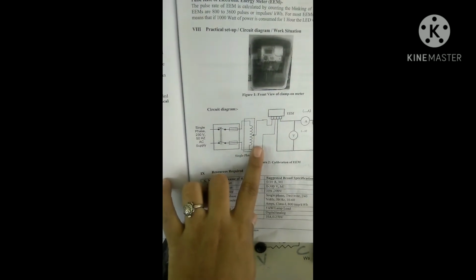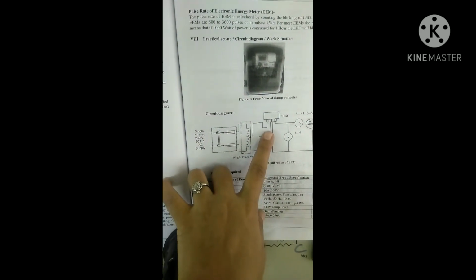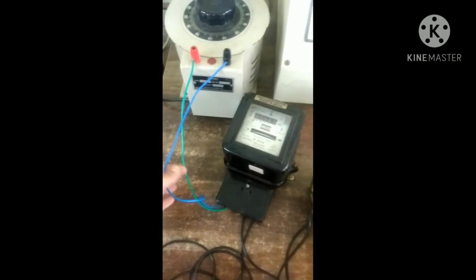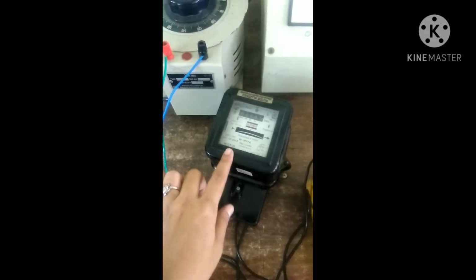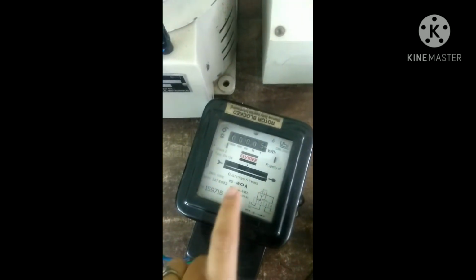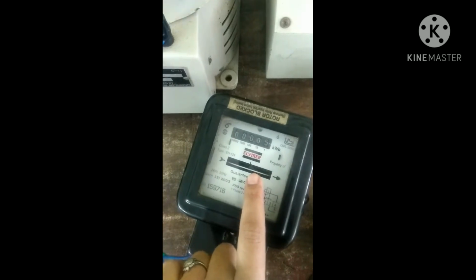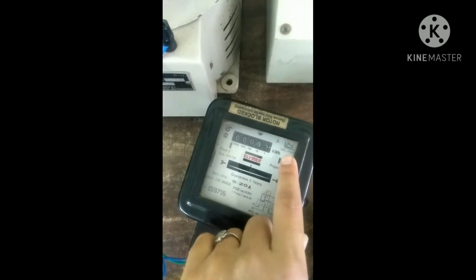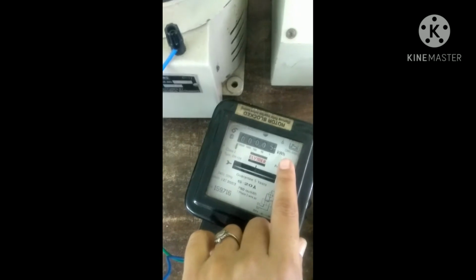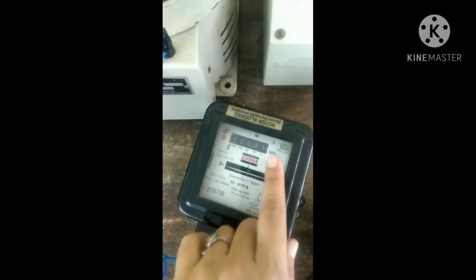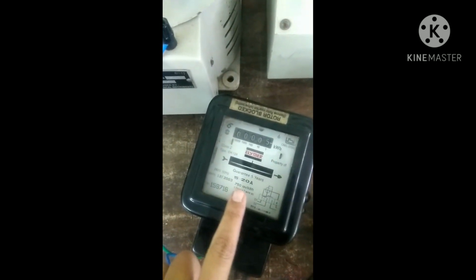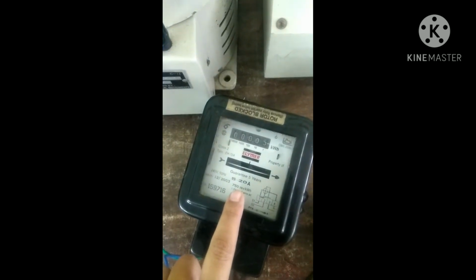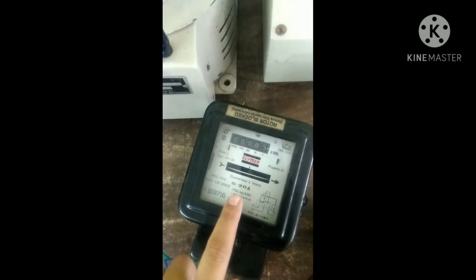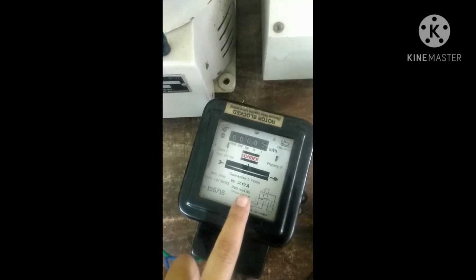So first, this variac is connected to input terminals of the energy meter. This is your energy meter. You can see there is an aluminum disc. This is registering mechanism, and unit of energy is kilowatt hour. And this is your energy meter constant, that is 750 revolution per kilowatt hour.